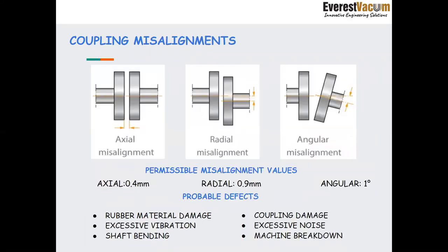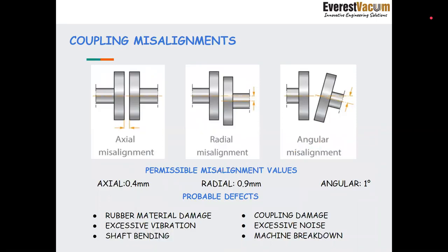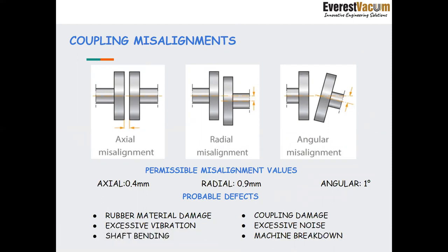Then these are the coupling misalignments. It could be either axial, radial or angular misalignment. What is permitted is 0.4 mm axially, 0.9 mm radially, and 1 degree angular. So what can be the probable defects if it is misaligned? Rubber material will be damaged, there could be excessive vibration, the coupling can get damaged, there can be excessive noise, and it can even lead to shaft bending and machine breakdown ultimately. So that much is the criticality of the coupling mounting, so we need to take care of this.